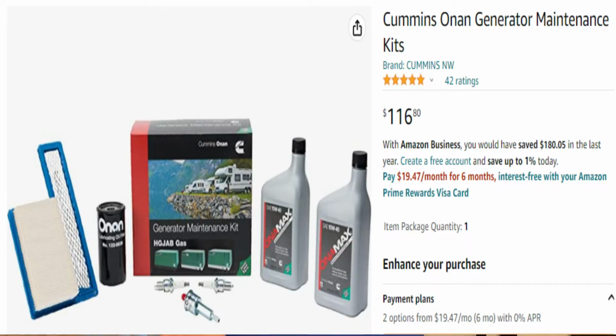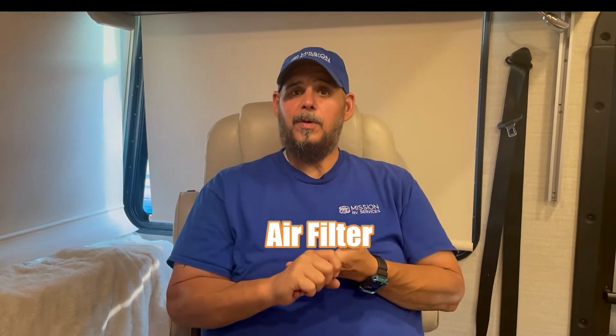So very important. This is something the DIYer can do themselves. So look at your manual, check your service manual on this part. Follow those recommendations. Make sure you're getting the proper oil filter. We recommend that if you're doing an Onan oil change on an Onan generator, that you just go ahead. You can go on the old Amazonian website and you can pick up an Onan, basically your first oil change kit. It comes with 2 quarts of oil, which is what that generator takes. It comes with an oil filter. It comes with an air filter. So who knew there was an air filter on their generator? Not a lot of people do. But at your 150 hours, that is what you're going to do, is you're going to do that oil filter and air filter change.